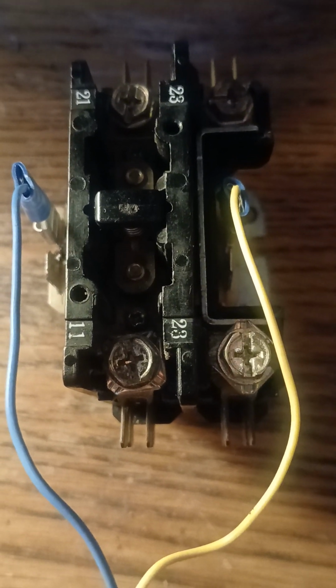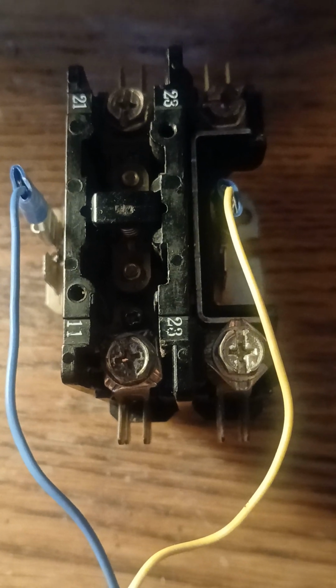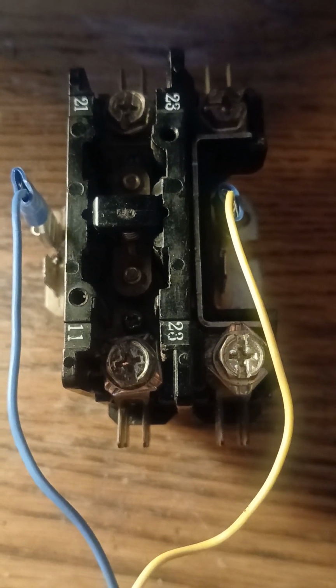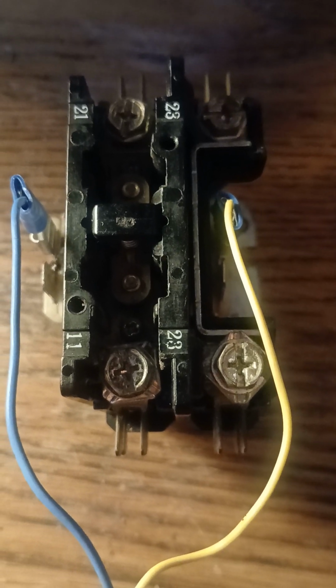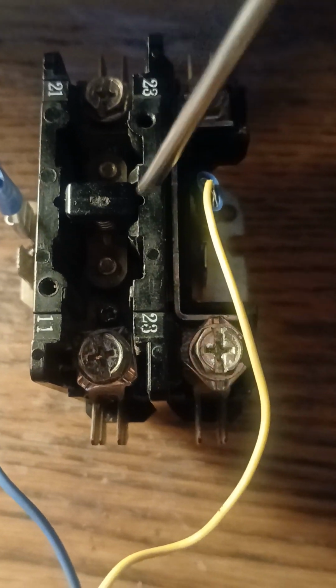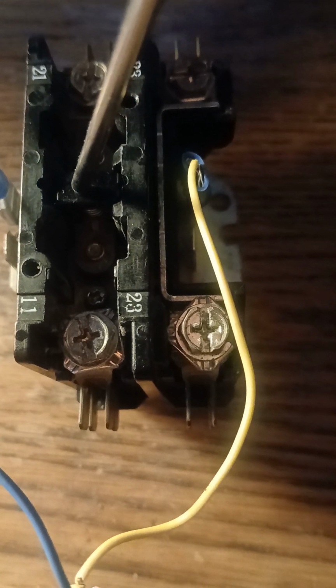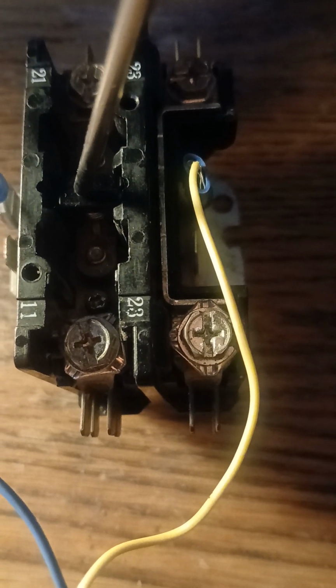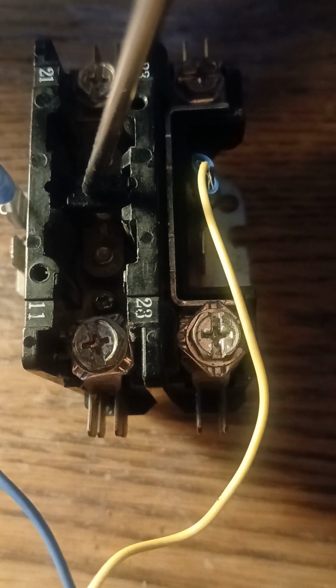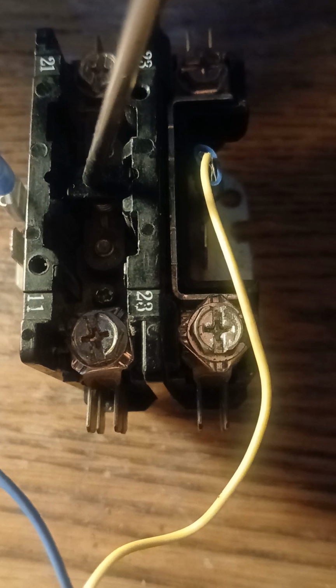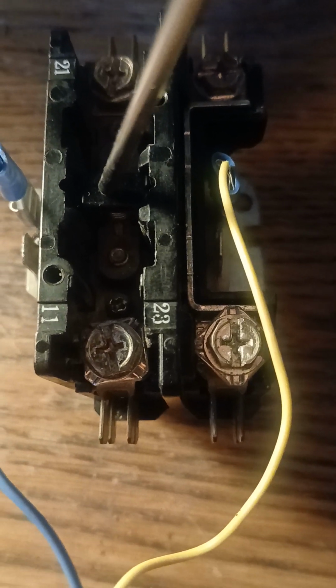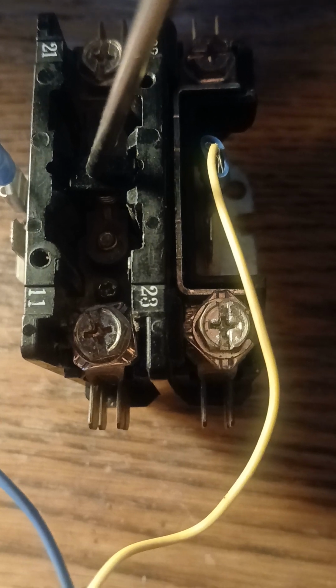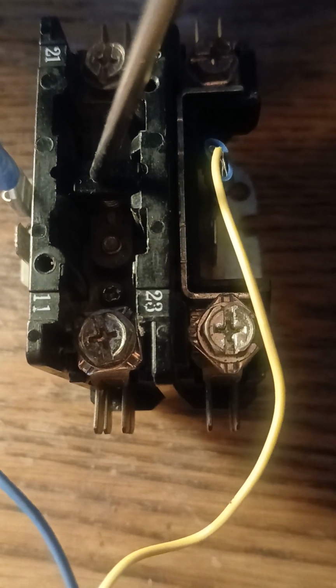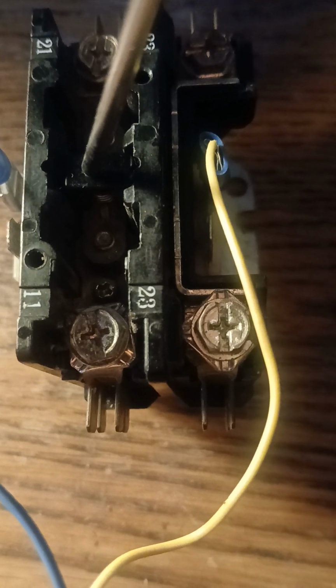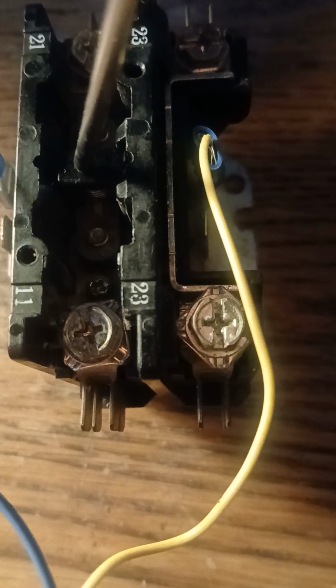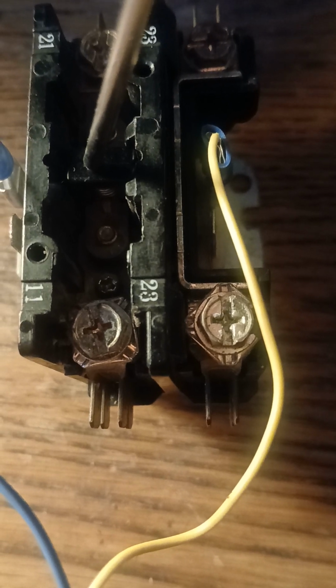That sounds wonderful, operating the condenser and the fan motor, but do keep in mind that it also cuts it off when it's not needed. So if this contactor gets welded shut and will not cut off, you may need to just power down the system until you get a technician to change it, or change it however you decide you want to go about changing it, whatever method you use. Because if this contact stays in, if it's welded shut, that motor and compressor have the potential to just continue to run, and it may end up burning itself out and shorten the life expectancy.